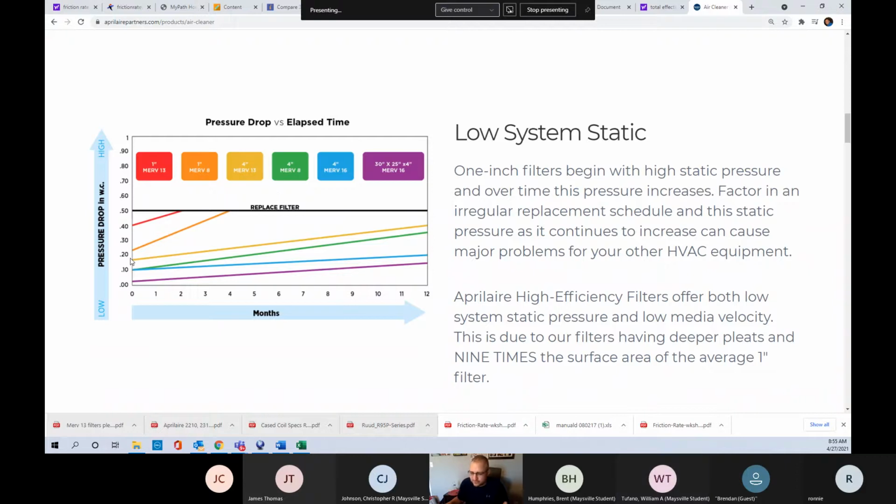So as you can tell, I'm just not a huge fan, but you're going to see them everywhere. So that may be a good opportunity if you understand how this works and how it can affect your system. And it might be a real good time, if you're there changing a motor, to look at their filter system and say there's a possibility that, maybe look at their duct sizing too, but there's a possibility that if we were to upgrade this filter, we could prevent this from happening again, because you're pulling a lot of static across this.